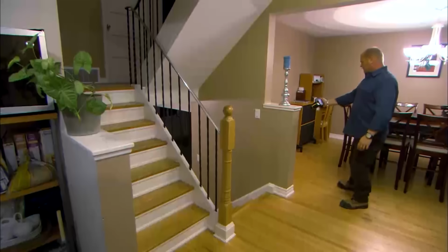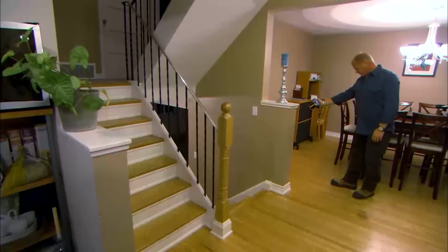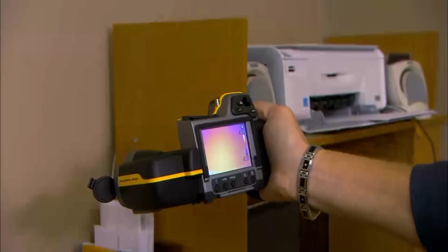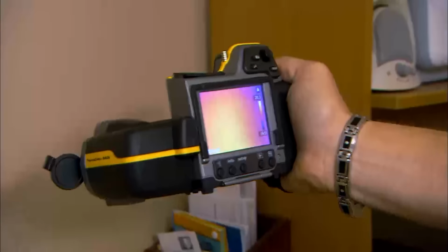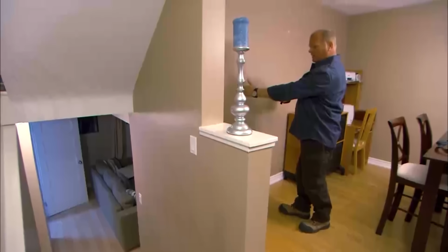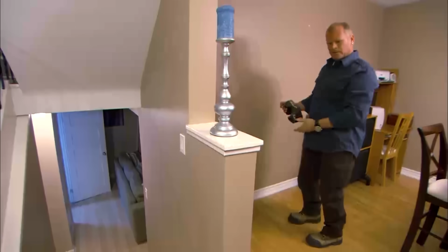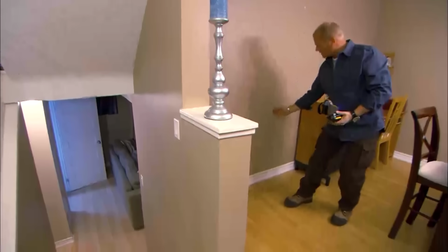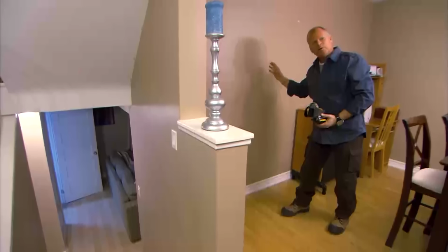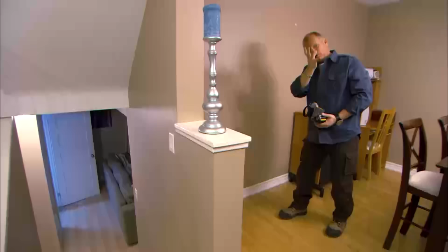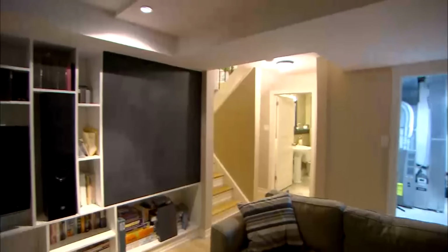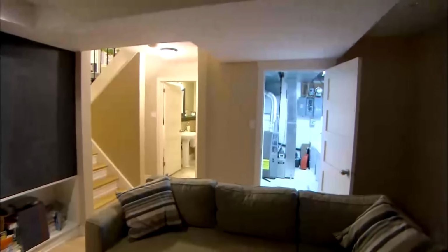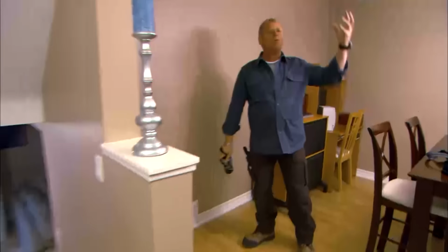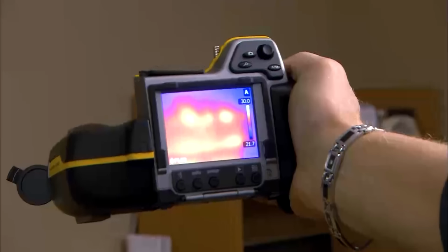Right now, if I scan across the wall, I'm looking for changes in temperature. As I come down, I'm seeing a big yellow spot right here. I'm having escape air in the floor joists, because I don't see the lines coming up this wall and through the floor. They're probably coming up off the trunk that's in the basement, across the bulkhead. But it's telling me there's heat escaping, and it totally makes sense to me, because if they're freezing cold upstairs, I have a breakage somewhere. It's not blowing where it's supposed to. What does that mean? More damage. More damage.